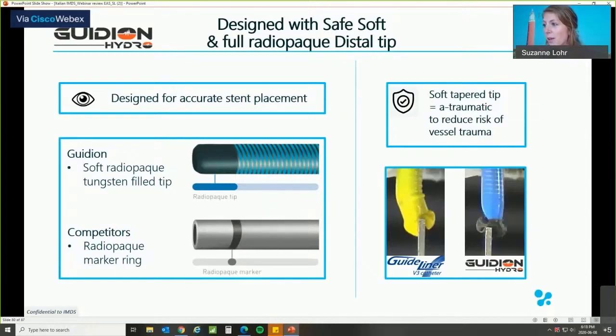Another very important thing for guide extensions, since they are quite bulky and large compared to, for example, microcatheters, is that the distal end is very safe, because you never know if you feel an obstruction or any kind of reason. You don't want any damage to the vessels. The disadvantage of this stiff metal marker ring on the guide extensions of the competitors is that, as you can see in the picture on the right, when you push a rigid object towards the distal end of a guide extension, the metal ring will always remain its shape, which can cause some kind of risk to the vessels, since it can affect the vessels.